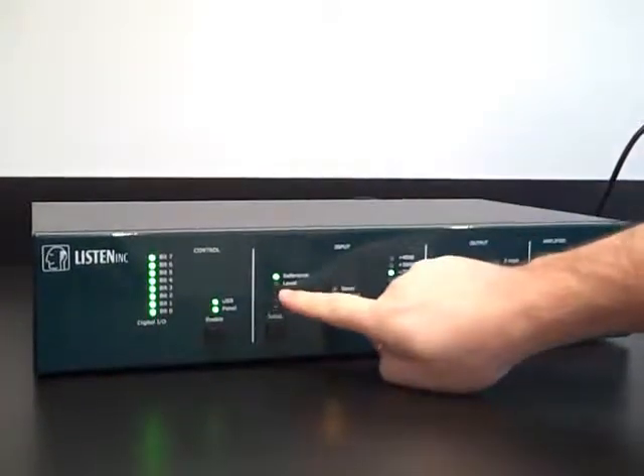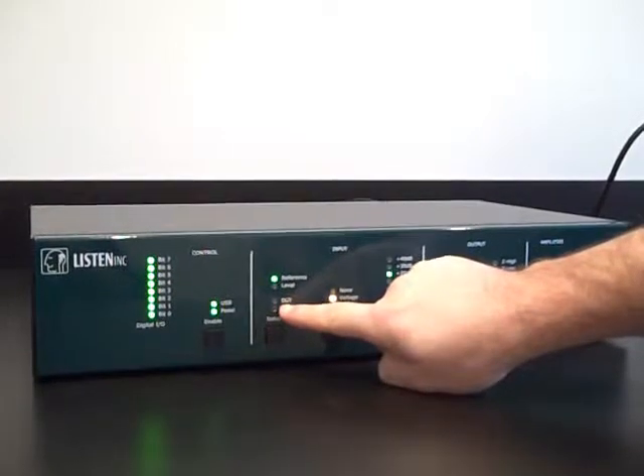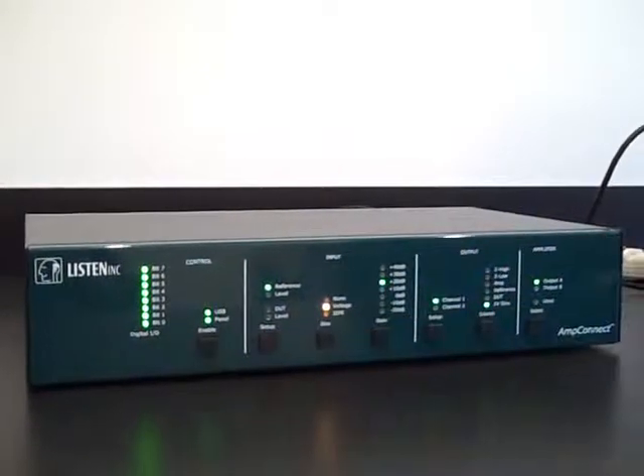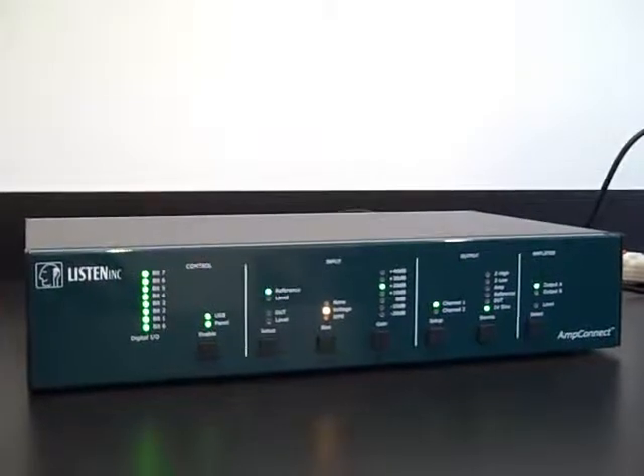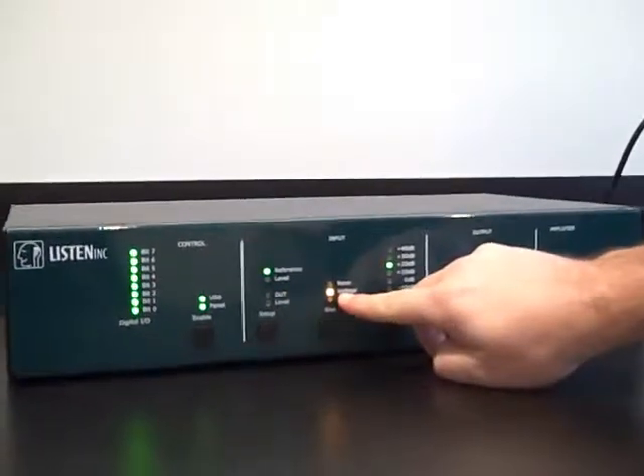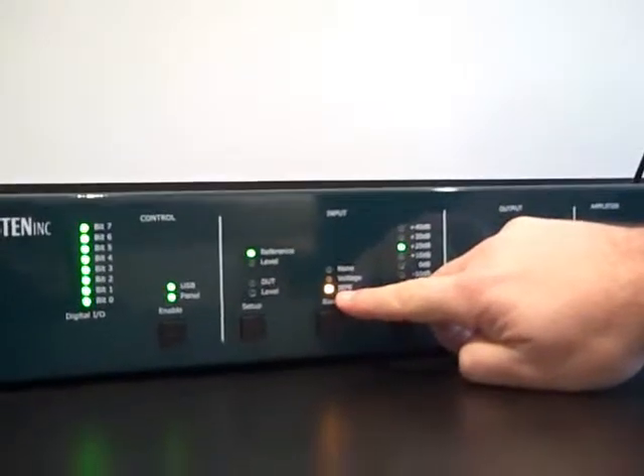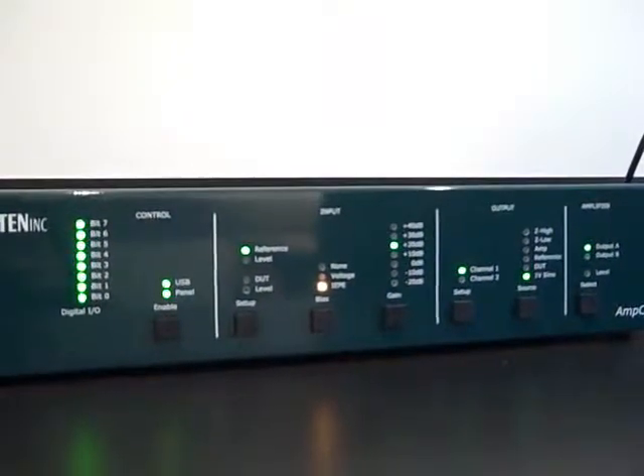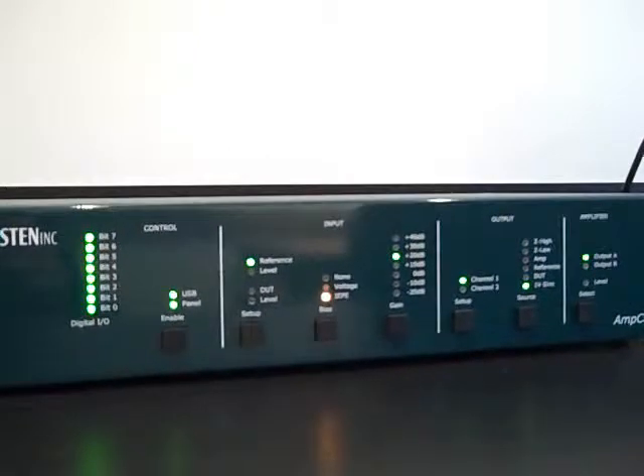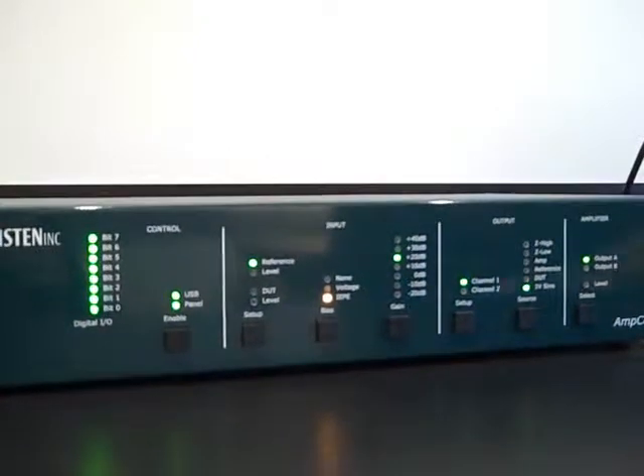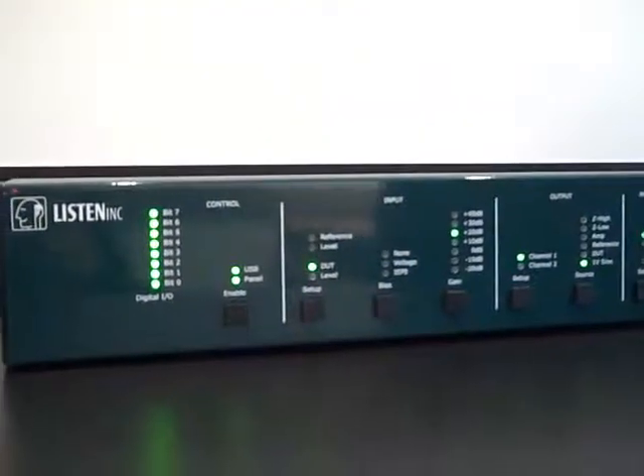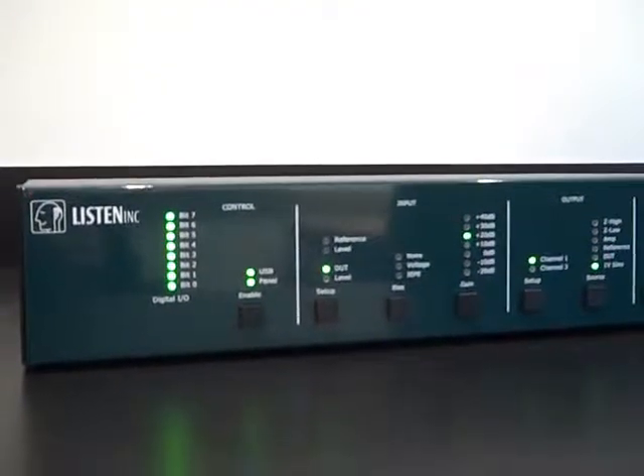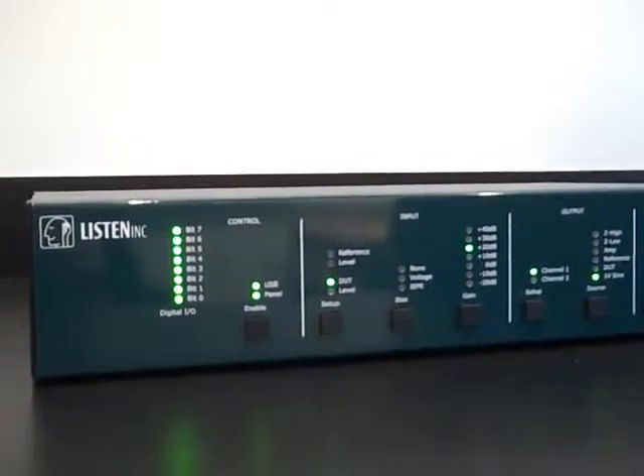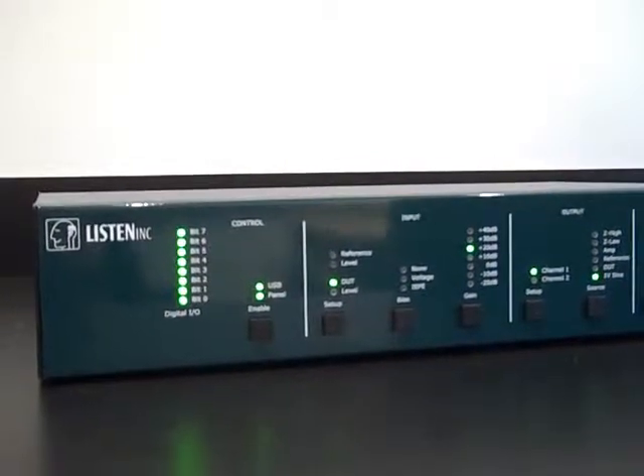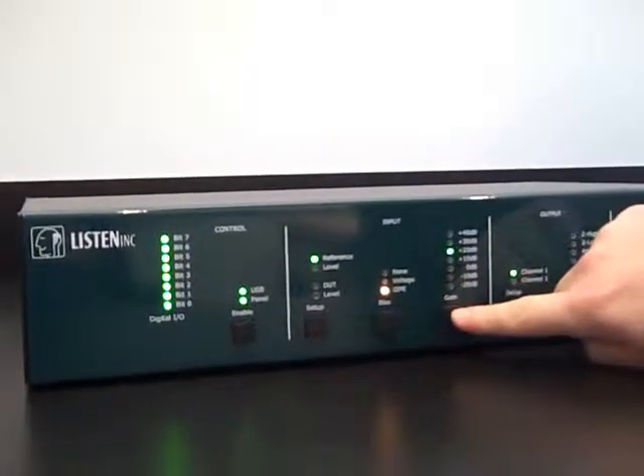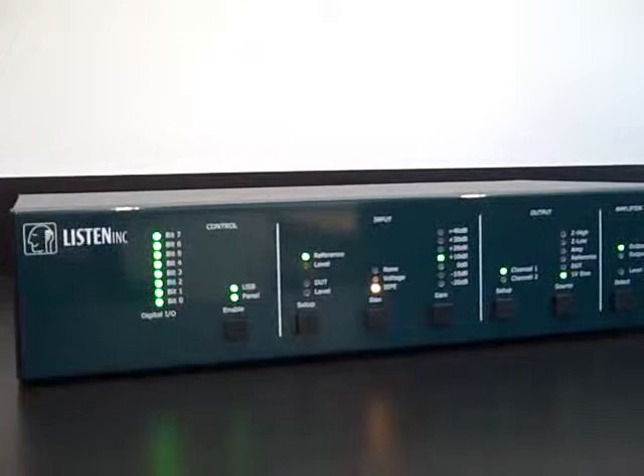There are two inputs on AmpConnect that we have labeled reference and DUT. The reference input is designed to work with a reference microphone, and we can supply either voltage power or IEPE. The voltage works with our Listen SCM microphones, and IEPE can be used with microphones from companies such as B&K and Gras. The DUT input can be used for testing microphones. This way you have your microphone under test and your reference microphone for calibration both connected at the same time. Each one of these channels can also have its own output gain, independently set.